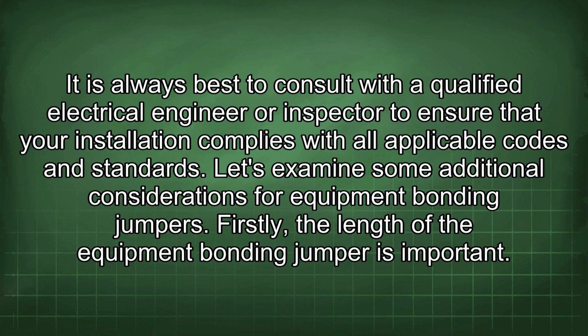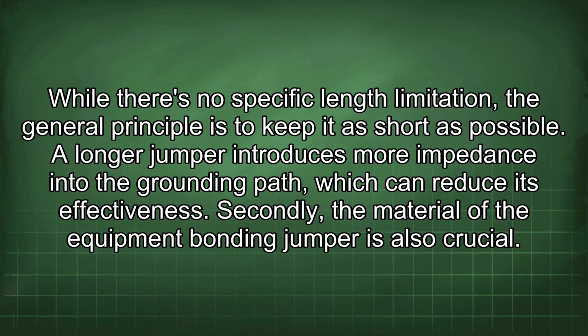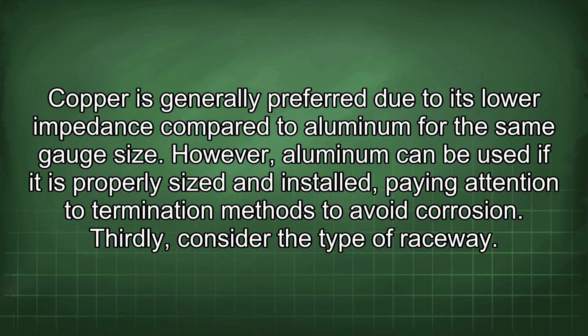Let's examine some additional considerations for equipment bonding jumpers. Firstly, the length of the equipment bonding jumper is important. While there is no specific length limitation, the general principle is to keep it as short as possible. A longer jumper introduces more impedance into the grounding path, which can reduce its effectiveness. Secondly, the material of the equipment bonding jumper is also crucial. Copper is generally preferred due to its lower impedance compared to aluminum for the same gauge size. However, aluminum can be used if it is properly sized and installed, paying attention to termination methods to avoid corrosion.